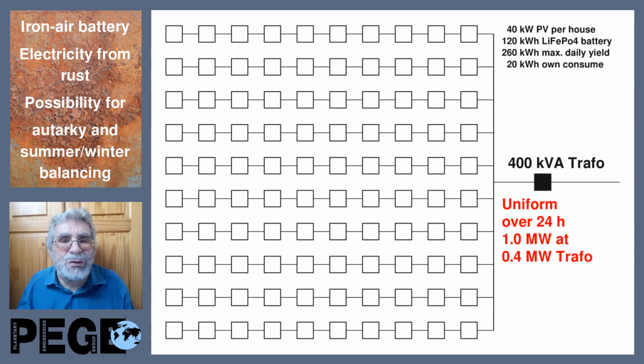Here we assume, in addition to the 40 kilowatt photovoltaic, 120 kilowatt hours of lithium iron phosphate batteries. We assume a maximum yield day of 6.5 times the installed photovoltaic, so 40 times 6.5 is 260 kilowatt hours. And we assume 20 kilowatt hours on average of own consumption. Yes, we have to charge our cars. And in this case, the whole village will deliver equally 1 megawatt for 24 hours. But sorry, the trafo is still only 0.4 megawatt, and we still need a huge grid expansion to do this.